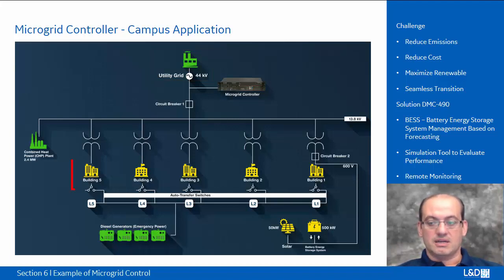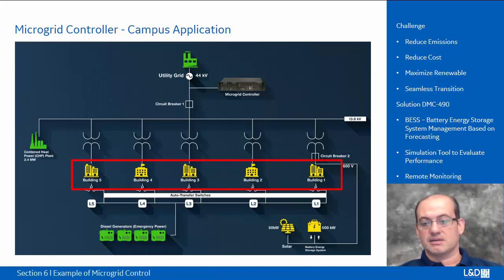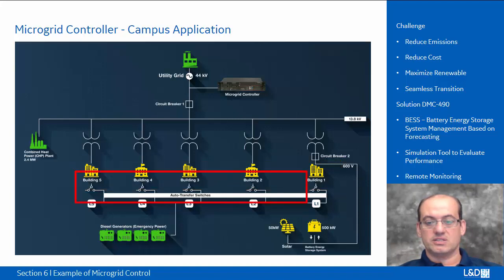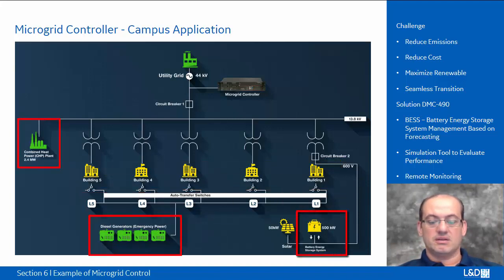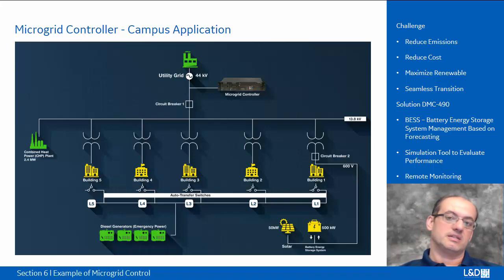As you can see, there are 5 buildings and many points of generation - diesel generation, a combined heat and power plant, and a battery system. The idea was to turn on the battery system when you can consume power stored at a cheaper tariff, and turn on the generators when required to provide power, sectionalizing areas that are not very critical when there isn't enough power produced to maintain the critical loads.